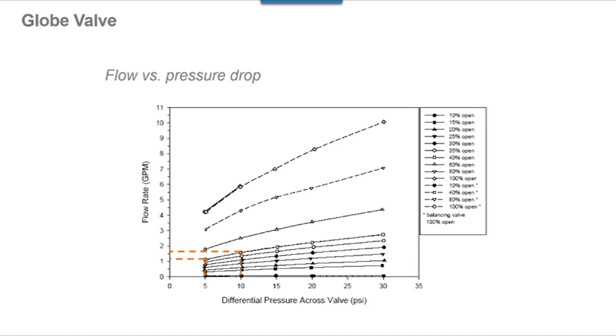Okay, so right off the bat, we know this is overflow. But let's think about it in this perspective. Half a gallon from one valve isn't that big of a deal. If it's only one valve, yeah, probably not. Probably leak that much in the system, maybe. Yeah, I mean, we're not talking about a lot of water. But what if this is a series of half-inch reheat valves?